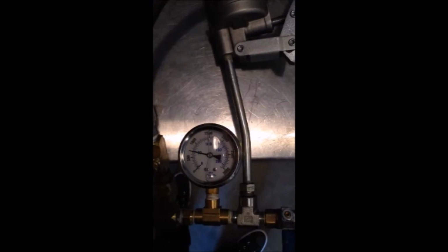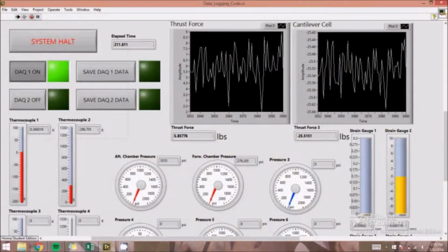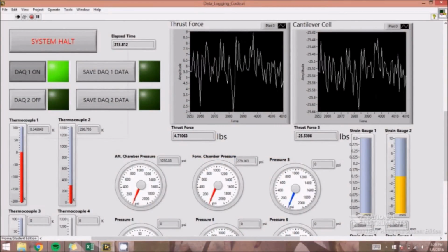For the pressure transducer, we used a grease gun with a gauge to apply pressure up to 1000 psi. The dial went up close to 1000, and the graphical interface on the computer showed close to 1000 as well.